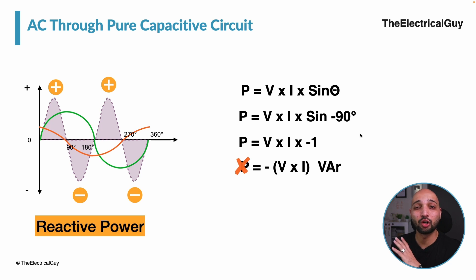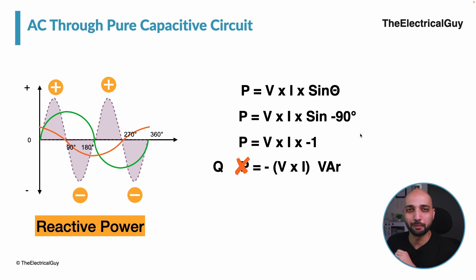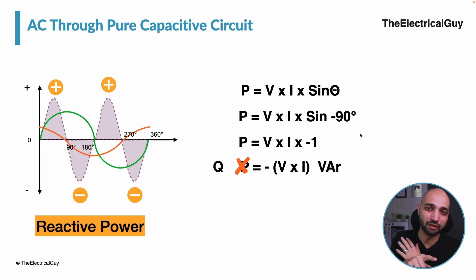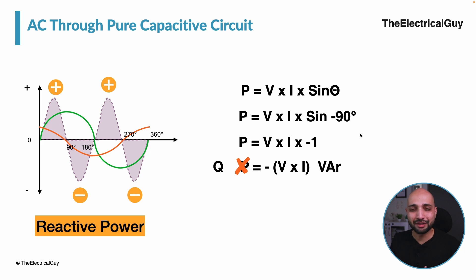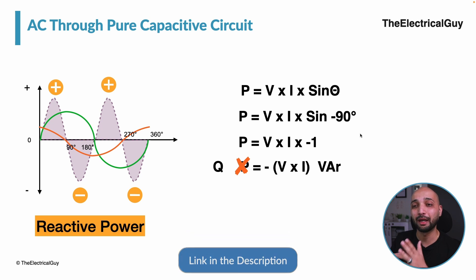Since this is a reactive power, the unit is volt-ampere reactive or KVAR. We cannot indicate it using the letter P — P is for active power only; Q is used for reactive power. The reactive power here is negative, which means the capacitive circuit is supplying power back to the circuit rather than consuming it. Because of this property, capacitor banks are specifically installed in power systems to improve power quality by supplying the necessary reactive power to the circuit.